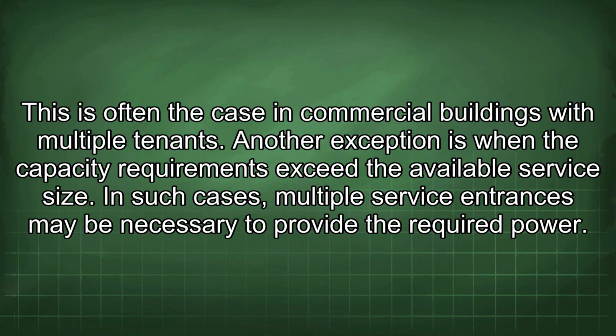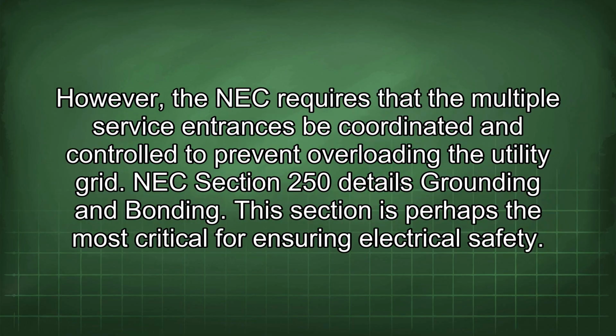This is often the case in commercial buildings with multiple tenants. Another exception is when the capacity requirements exceed the available service size. In such cases, multiple service entrances may be necessary to provide the required power. However, the NEC requires that the multiple service entrances be coordinated and controlled to prevent overloading the utility grid.